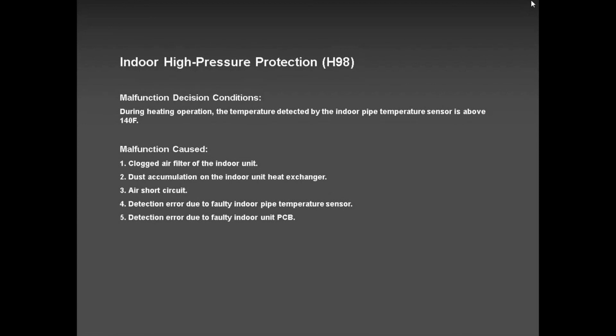H98 is an indoor high pressure in heat mode. You will not get this problem in cool mode, guys. It's an indoor unit that is creating this error H98. I have noticed when a guy is installing a 5-zone and 5 units are running, no problem. The moment they start switching off all units and operating just one little small unit, now what happens? The condenser, which is the indoor unit, becomes too small. The surface area is small, and that indoor unit cannot handle the 5-zone condensing unit. So that's when you have the H98.